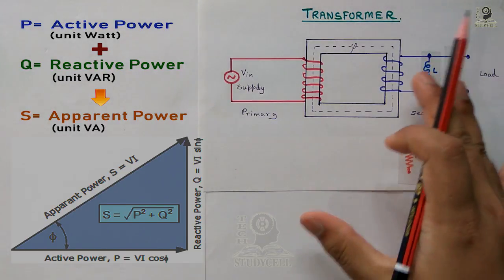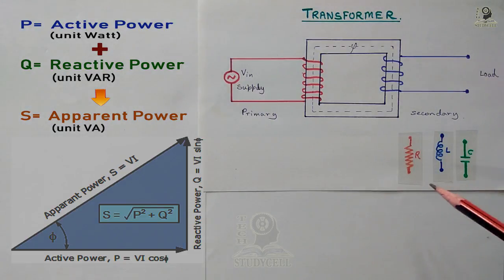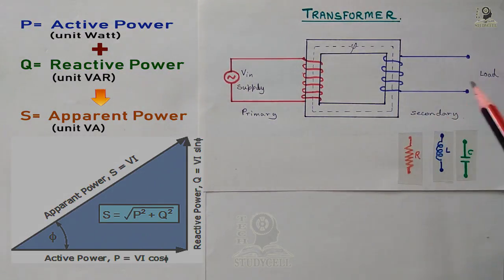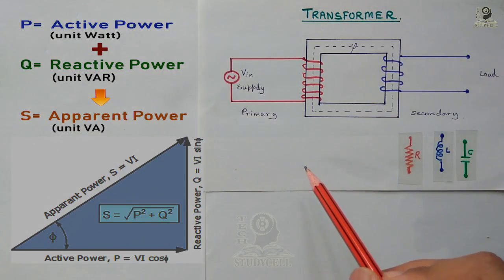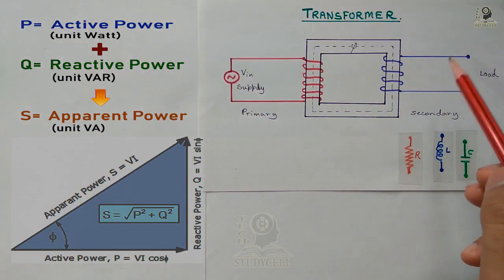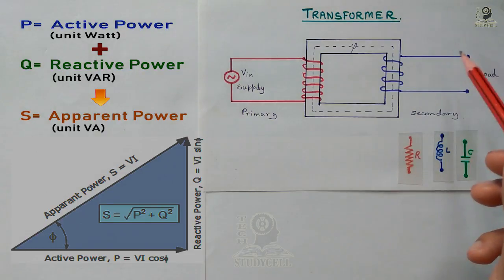In practice, there are no loads which are purely resistive or purely inductive. When supplying any electrical circuit or any load, we have to supply both active and reactive power. So we have to supply the apparent power, whose unit is VA — voltage ampere. As we give supply through a transformer, the transformer has to supply both active and reactive power to the load. So the transformer is rated in kVA, or VA, or if the rating is much higher, then in MVA.